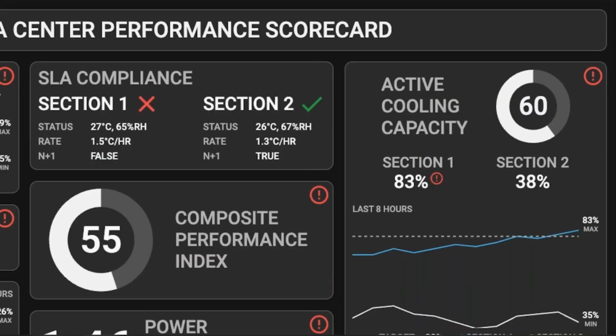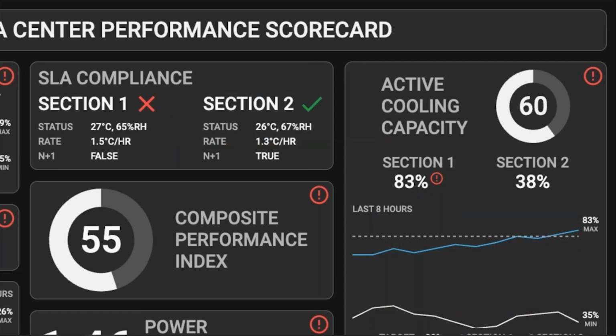The cooling part, again, really scares me, because what's happening? I have two rooms, section 1 and section 2. And I know in each room I have 5 CRAC units. So room 1 has 5 CRAC units and room 2 has 5 CRAC units. I see that my load in room 1 is 83%. So I know I've lost my redundancy over there. That's a big issue, because that does lead to an SLA violation. If I look at my temperature, my humidity, and my rate of change of temperature, they are still okay, but I've lost my N+1 situation, which is quite worrying, because if one CRAC unit now fails, then I will have an outage in that room, and that's something I really want to prevent.